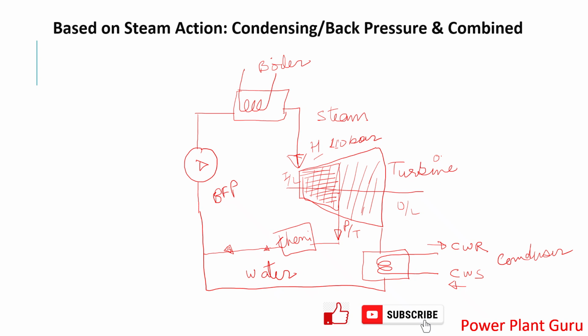Accordingly, you can build a steam turbine just like this big steam turbine, and then you can think of having that kind of back pressure turbine where you may not need this kind of arrangement, where you will have only a steam inlet, some part of the work through the turbine, then you have pressure and temperature remaining in the steam, and then you draw that steam and put it into your process plant. There you don't need your condenser and all.